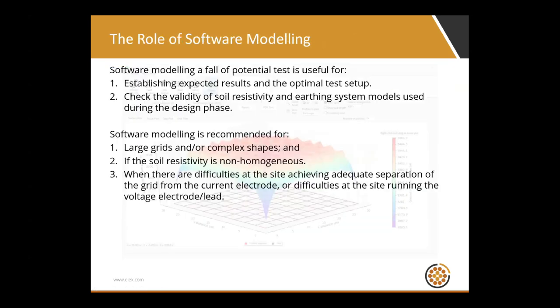So the role of software in this Fall of Potential or earth grid impedance testing is that it can establish or verify expected results. It can determine optimal test setup. It can test the validity of soil resistivity and earthing system models obtained during the design phase. Also, it can verify testing results. It's highly recommended to model the Fall of Potential test setup for large grids or complex shapes because of that ideal hemisphere assumption of the test, or if the soil electrical resistivity is non-homogeneous, which is almost always the case.